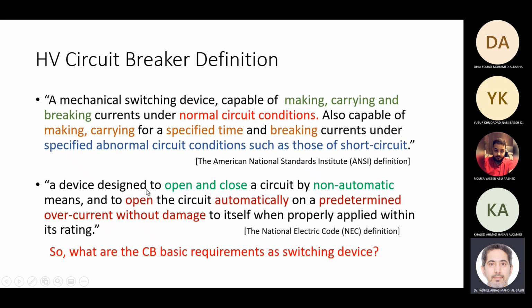While in the low voltage system, the definition is a device designed to open and close a circuit by non-automatic means, like manual, or to open the circuit automatically. Why does it open the circuit automatically? Because it has a protection device integrated with it, on a predetermined overcurrent, which is the settings, without damage to itself when properly applied within its rating. And when you choose a low voltage breaker rating and its breaking capacity properly, it can disconnect a short circuit without damaging itself.